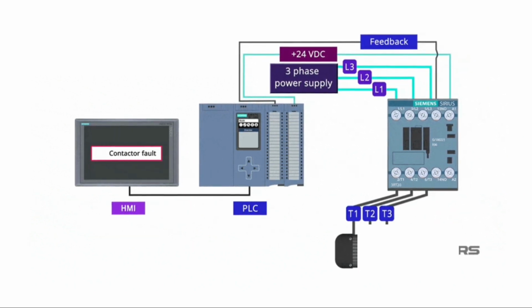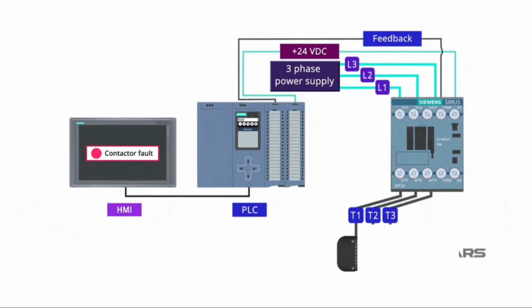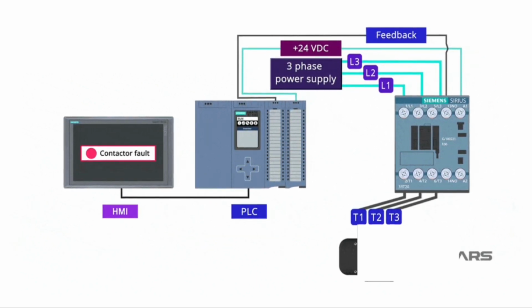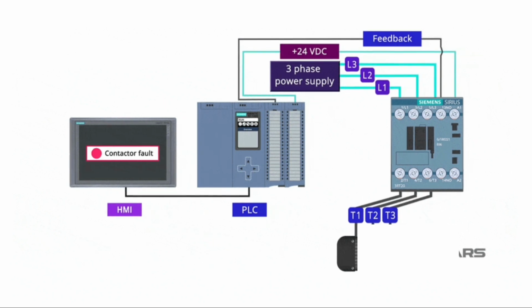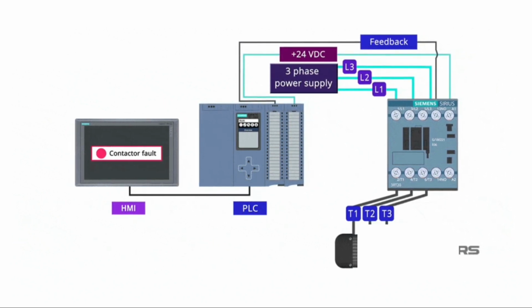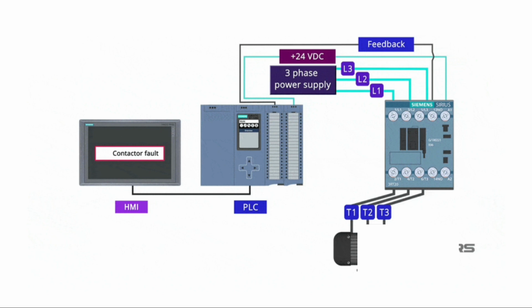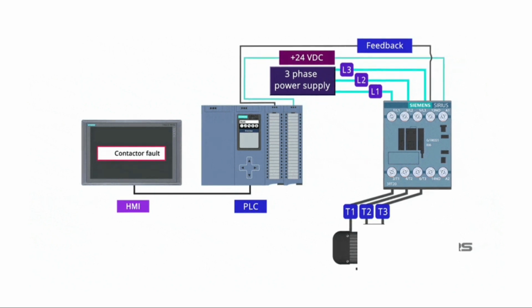We have discussed this more in our Level 2 PLC programming course, and there is a sample PLC program that shows why we always need to use a feedback contact and how to use that contact in the PLC program to get notified when the contactor is broken.